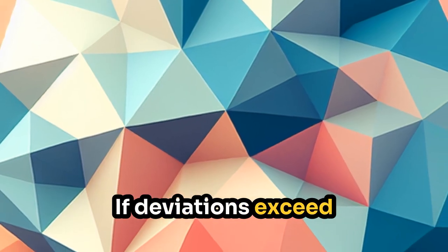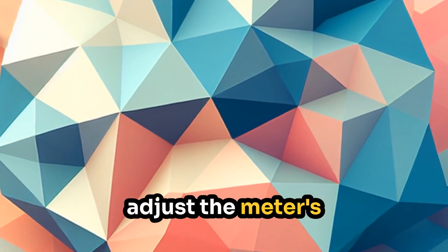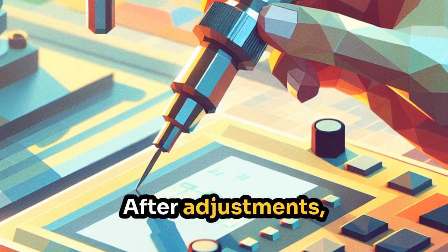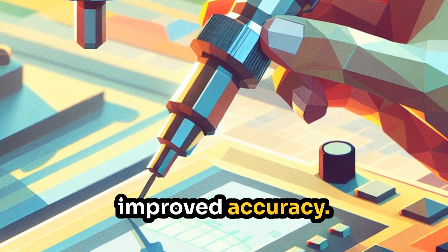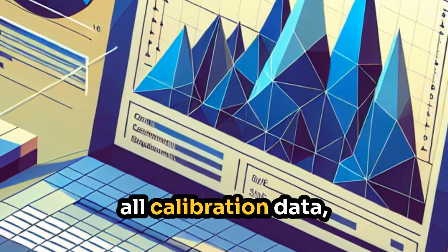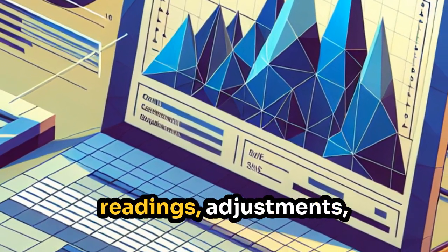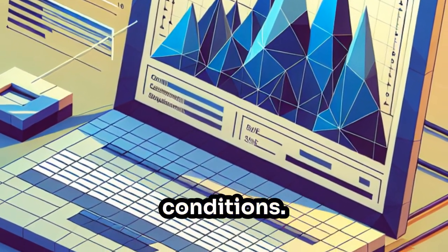If deviations exceed acceptable limits, adjust the meter's settings accordingly. After adjustments, retest to confirm improved accuracy. Finally, document all calibration data, including test points, readings, adjustments, and environmental conditions.